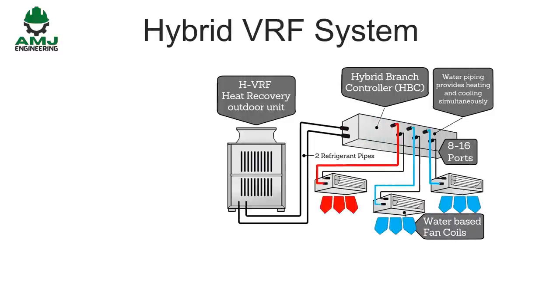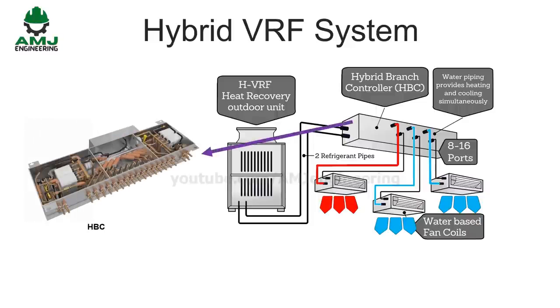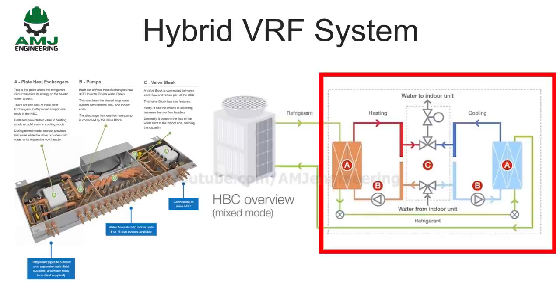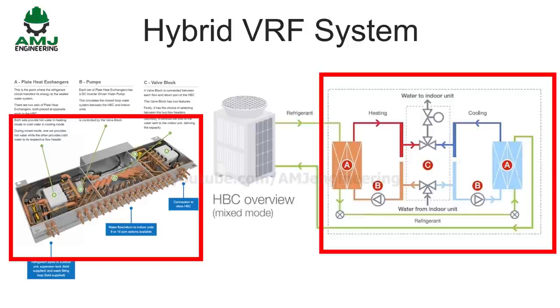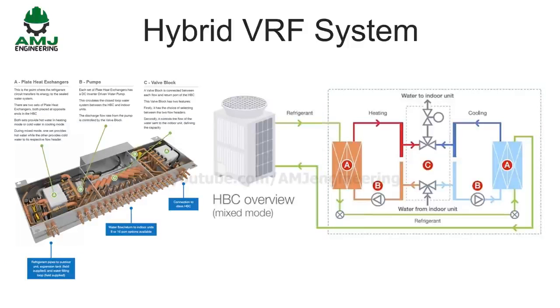Our last section is about hybrid VRF systems. Hybrid VRF is a unique 2-pipe heat recovery VRF system that replaces refrigerant with water between the hybrid branch circuit controller and the indoor units. At the center of the system is the hybrid branch controller, HBC, which is connected to the outdoor heat recovery unit via traditional refrigerant piping. On your right hand is a simple illustration of this HBC unit. There are 3 main parts in the HBC. A are the heat exchangers. B are inverter-driven pumps. C are the valve blocks. The HBC acts as the brains to the system.